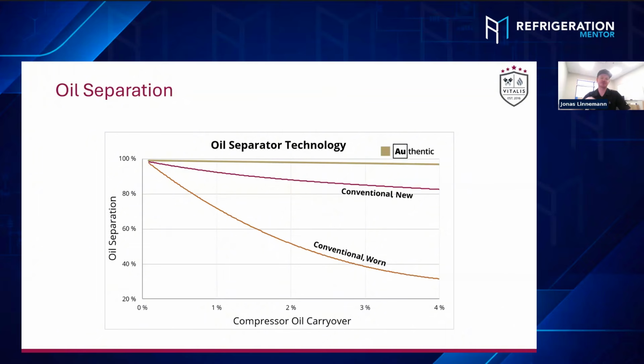And especially if a compressor had already some lubrication issues and the cylinder rings and stuff got worn out, then at some point the oil carryover is just getting super heavy. And then it's like, where's the oil at? Let's add some oil to it, because this one compressor has actually bad rings. It has nothing to do with anything else. So we add some oil to the unit, and then it runs for a little bit, and then it happens again 3 or 4 days later, and then until someone comes back, it all comes back and smashes a different compressor. Now you have two broken compressors instead of just one broken compressor. So I've seen a lot of that.